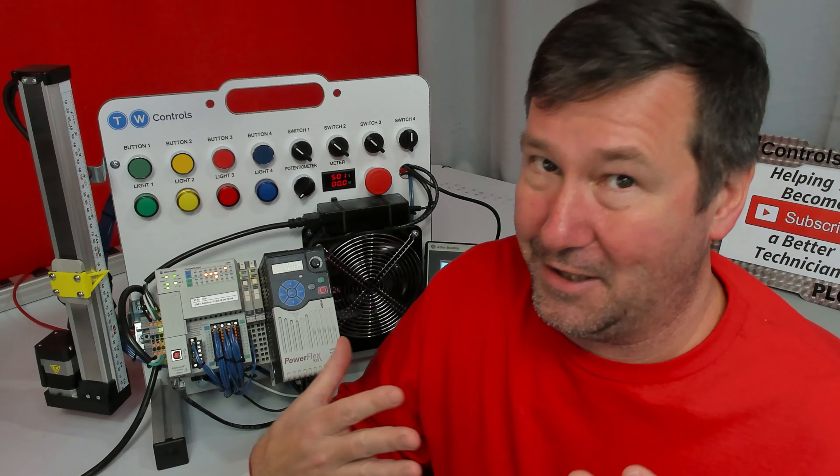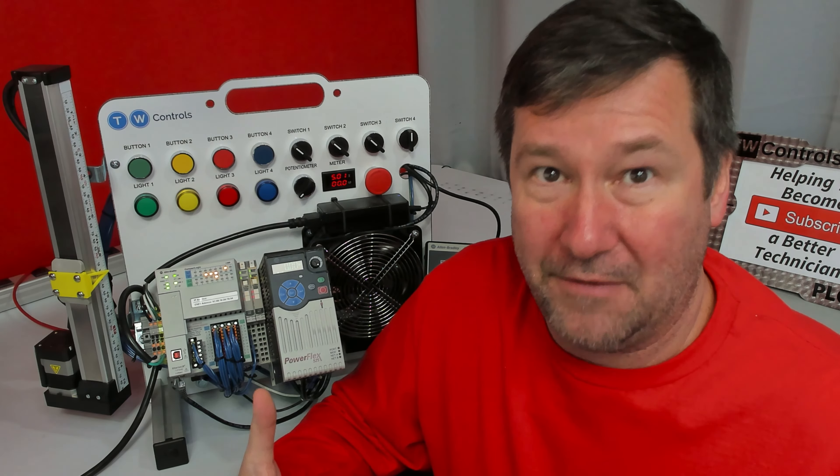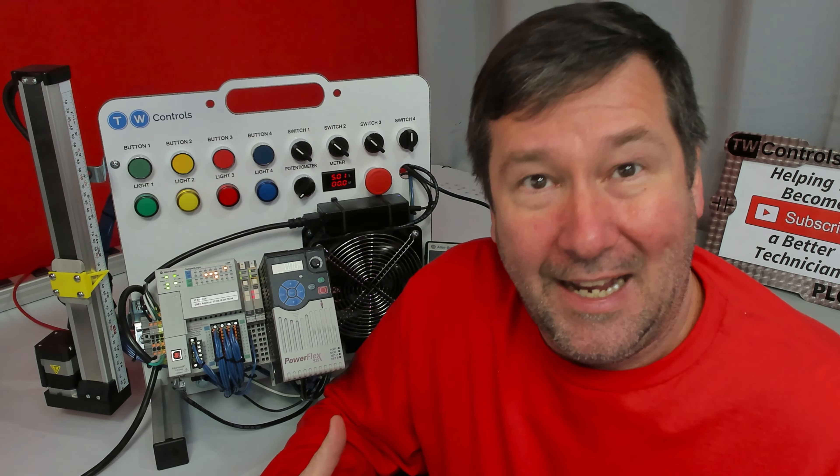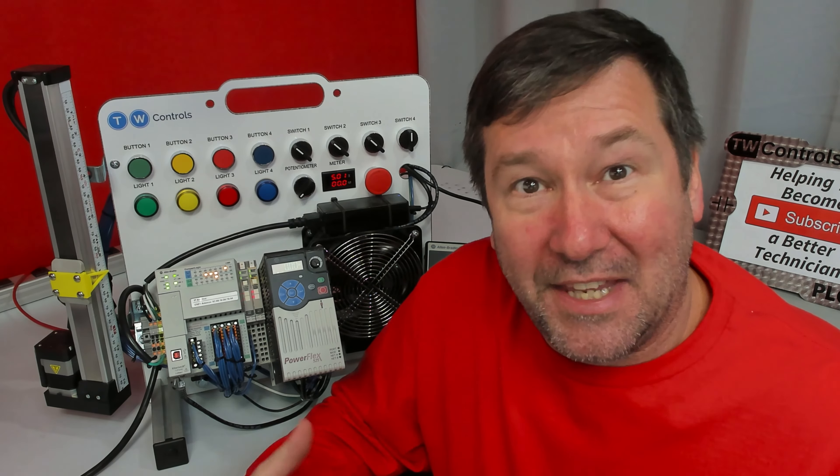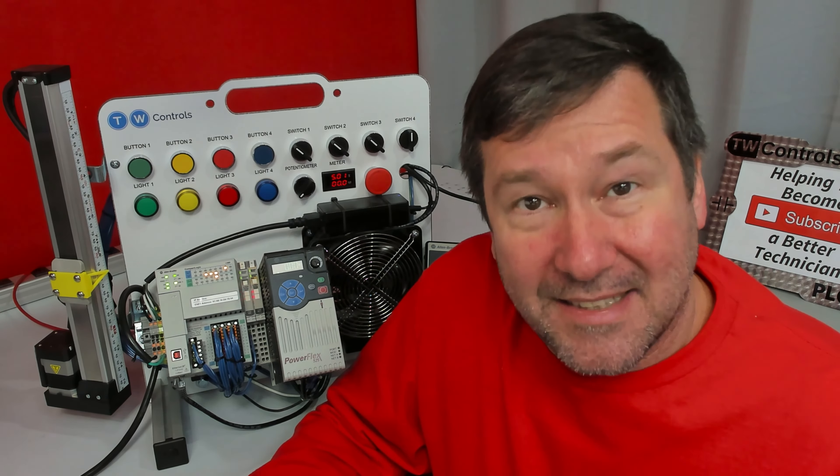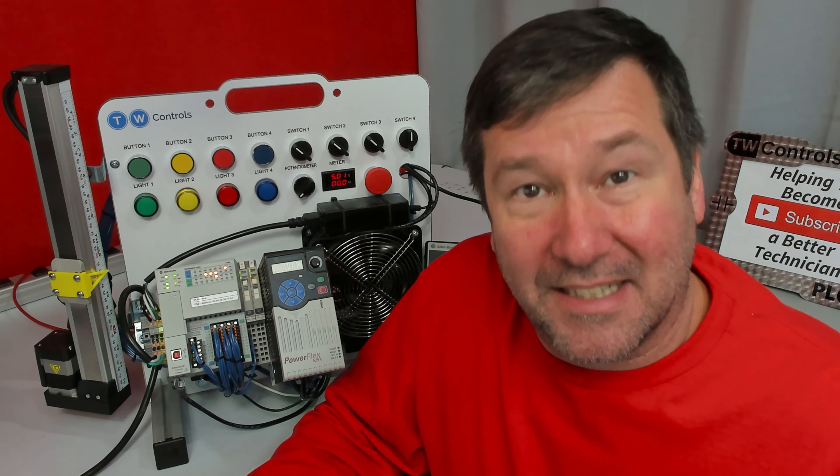Now, for most of what I do, I would call it cat 3. Now, here's where I have been going wrong all these years: I mostly work on 480 volt and below, and so I would think I need a 600 volt rated meter at cat 3.